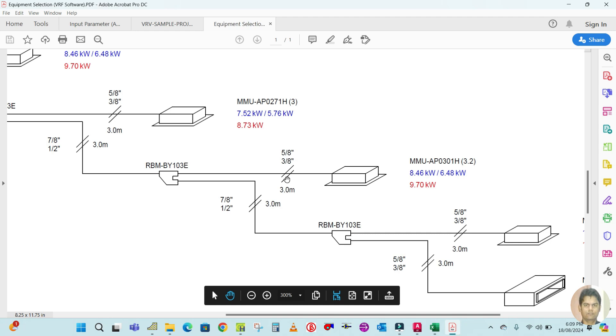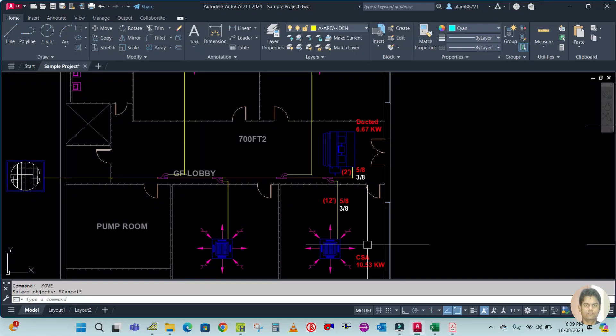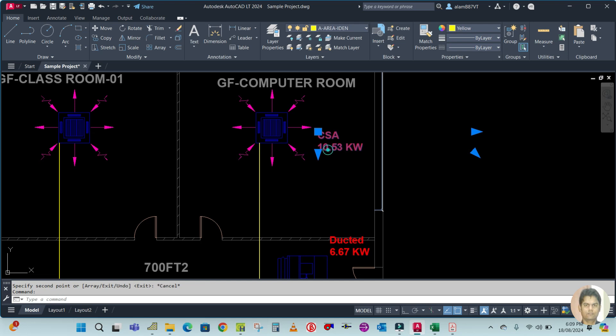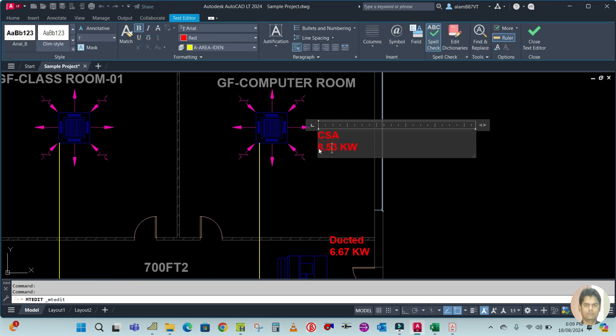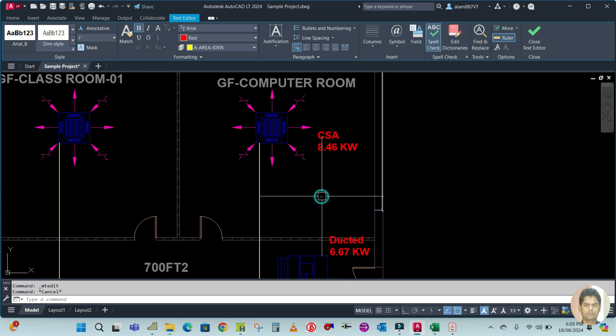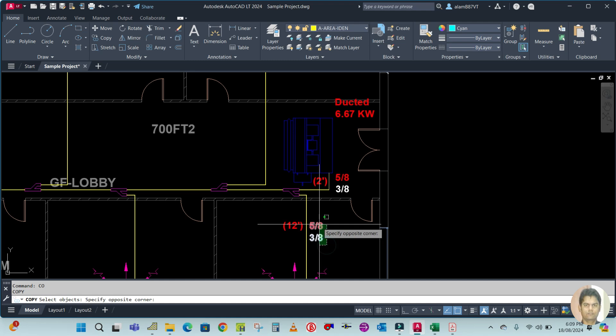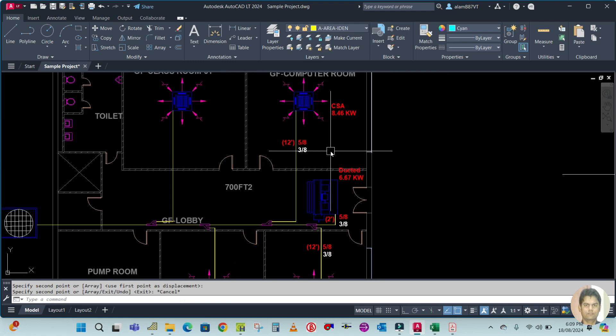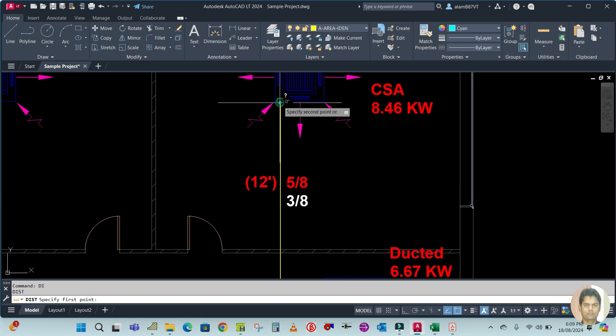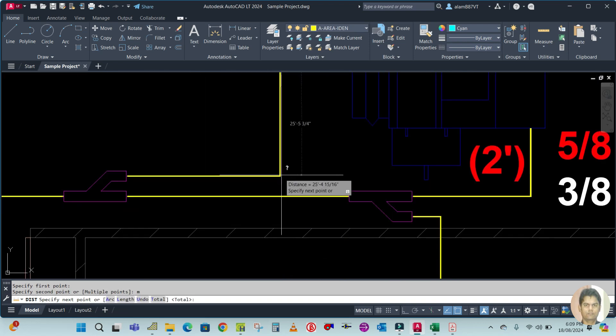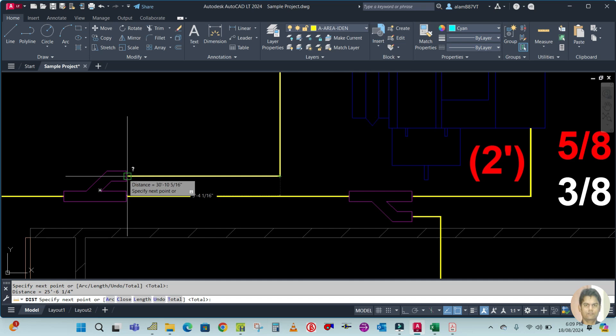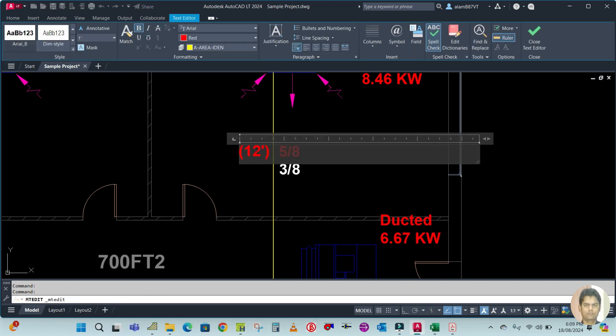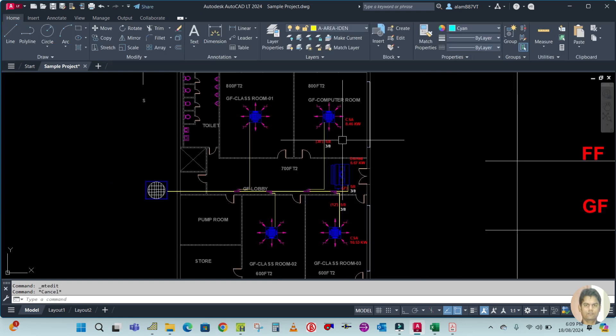The next cassette is 5/8 by 3/8 and 8.46 kilowatt. Similarly, copy here and double-click to edit — 8.46 kilowatt, pipe size 5/8 by 3/8. Copy and place it here. For the length, enter DI with M for multiple. The pipe length is 30 feet — double-click to edit: 30 feet.